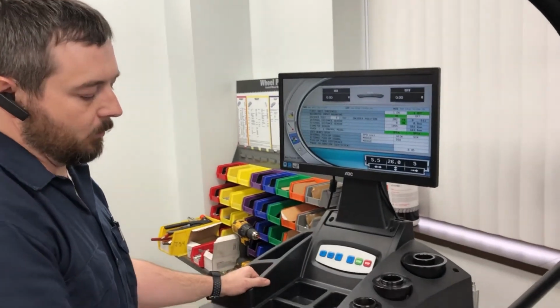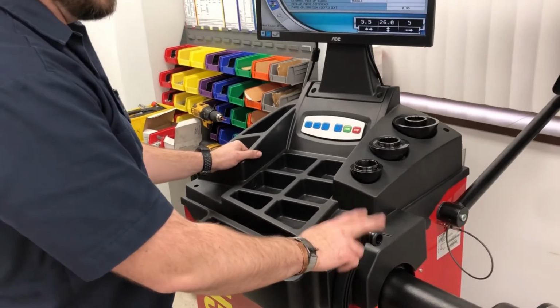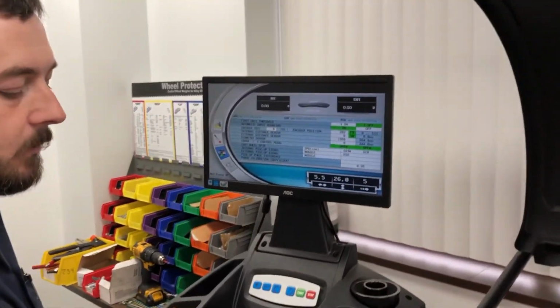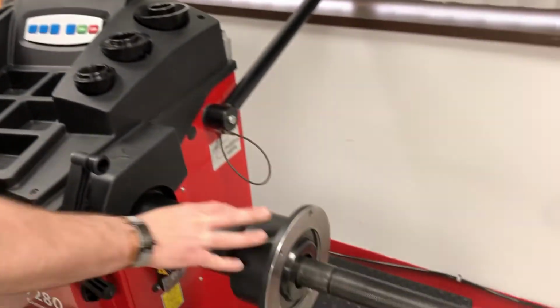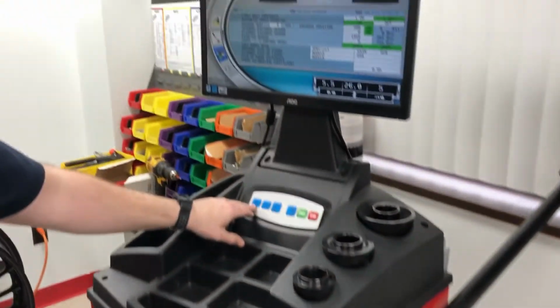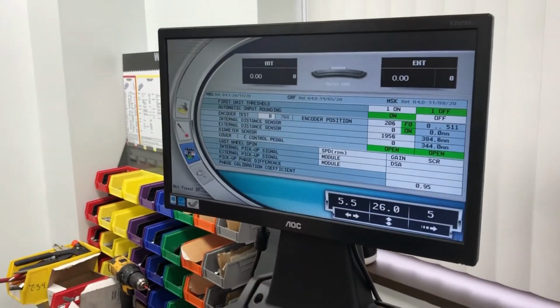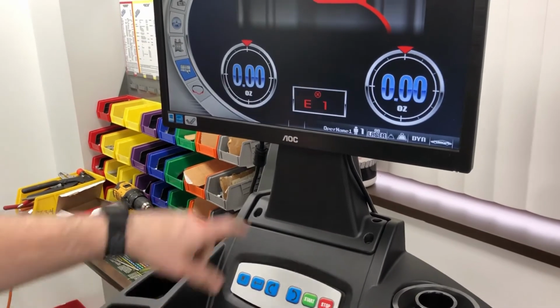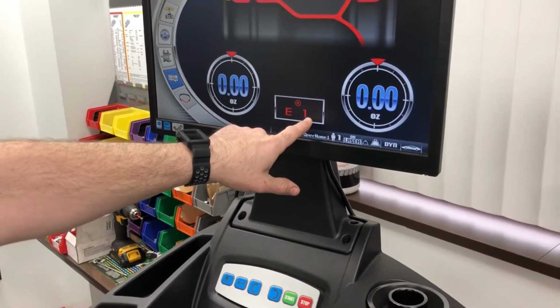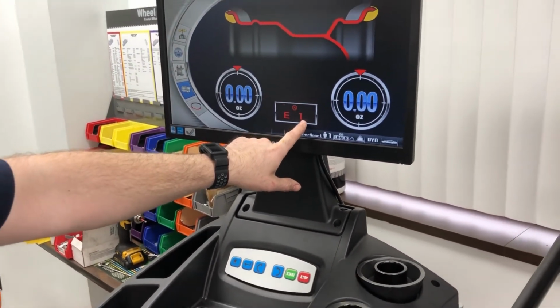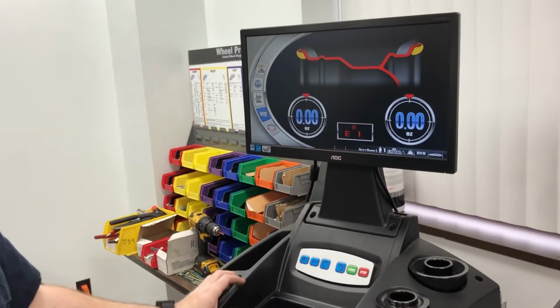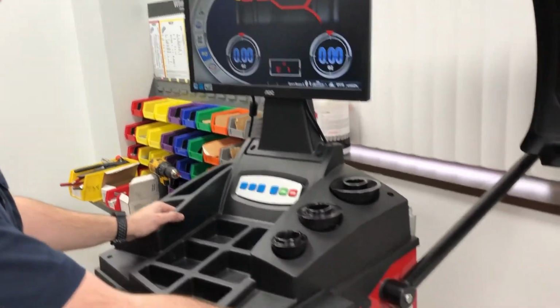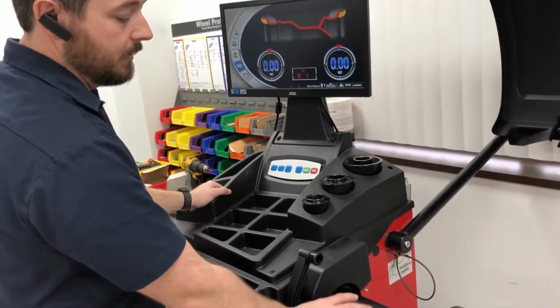Keep in mind that once your arm has been recalibrated, you will have to go through and recalibrate the spindle. We're going to press escape, which is the far left button, looks like an arrow pointing to a door. And we get our E1 code. This means that it has no sensitivity calibration. So you have to run through both your regular spin or sensitivity calibration and then your zero hub.